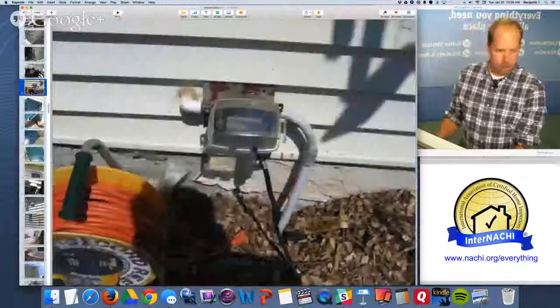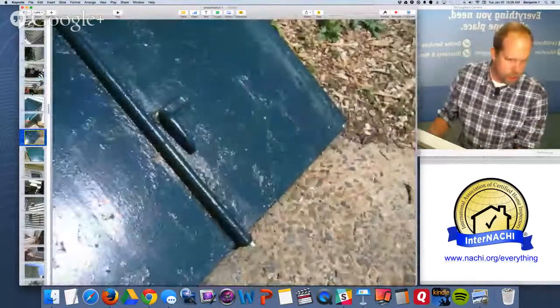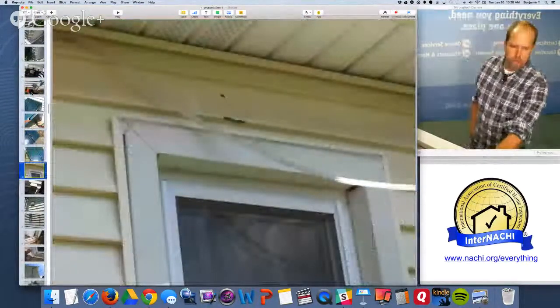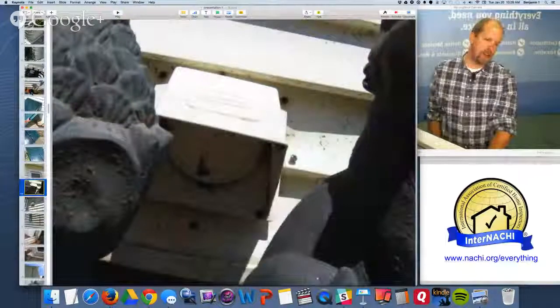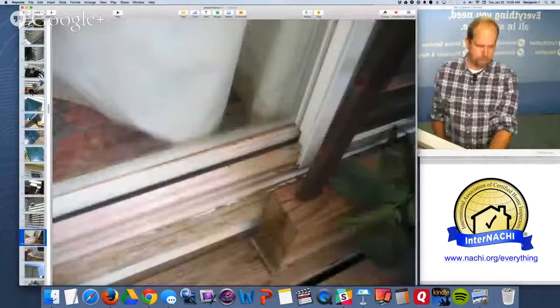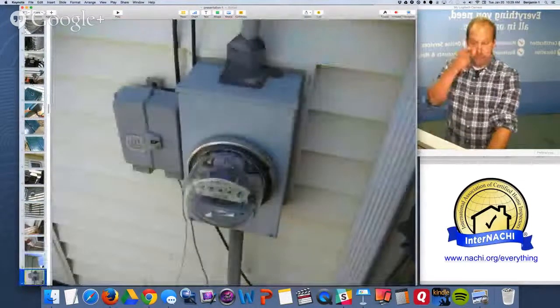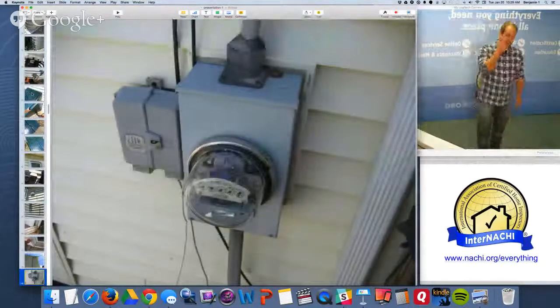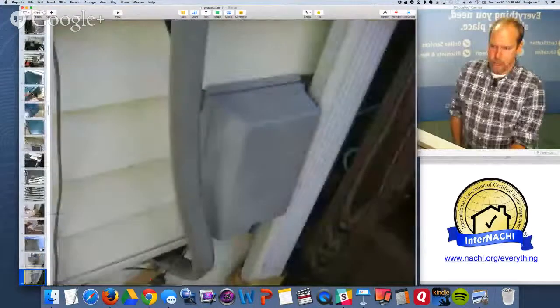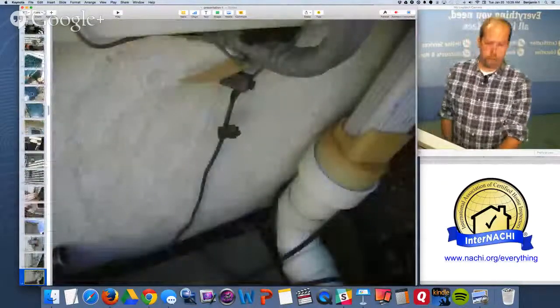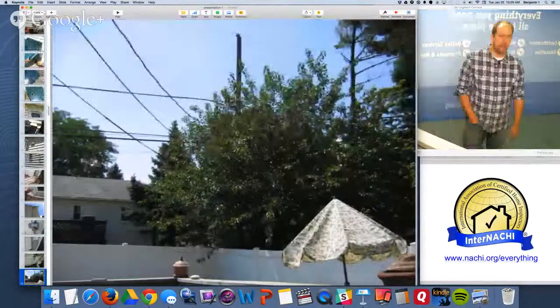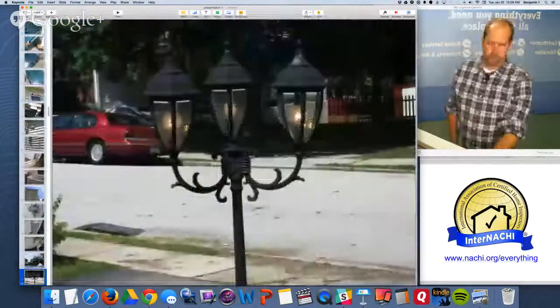There are some Bilco doors — a manufacturer brand — steel doors that go down to the basement. Some damaged vinyl siding. Looks like a dryer exhaust vent and bathroom vent — they took out a window and put that in. Electric meter, service amp. Overhead conductor, service line — the meter line going into the home. There's an updated line — it's 200 amp going into the home. Grounding wire. The overhead conductors are in the trees from the pole, service line.